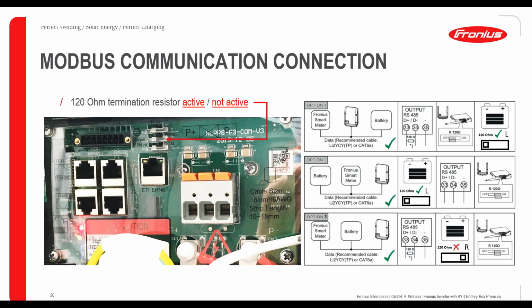Option 2 and option 3 are other options, where you can, for example, set the Fronius smart meter in the middle or the battery box in the middle. So as you see, depending on the position of the battery, the smart meter and the inverter, you have to set the 120 ohm resistor at the right place. Therefore, if the battery box is at the end, please make sure that the 120 ohm termination resistor is set to active.